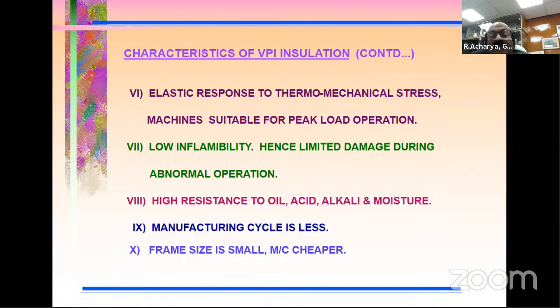Whereas this machine maintains a good, high flexibility and resilience, so it is suitable for very demanding duty. That's the reason why this is very frequently adopted for gas turbine applications, wherein the machine is designed to run almost 3 to 4 shifts in a day. It has a low inflammability, so that if any damage takes place, the damage extent is very less. Very high resistance to oil, alkali, and moisture. It is like a fit and forget.